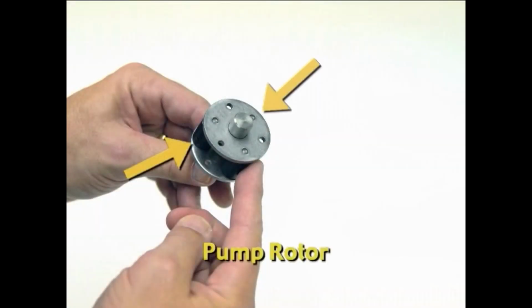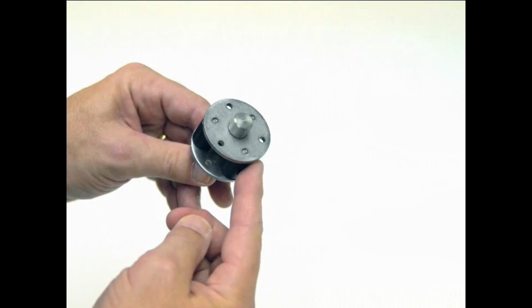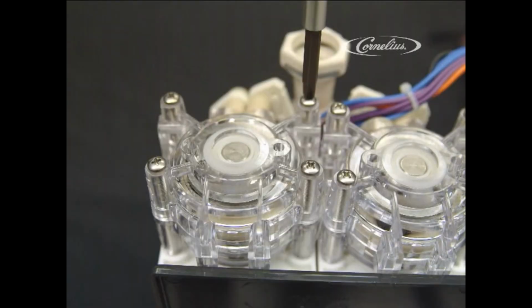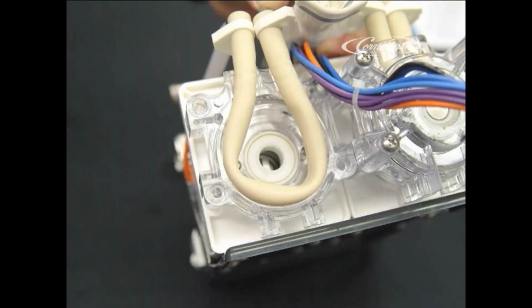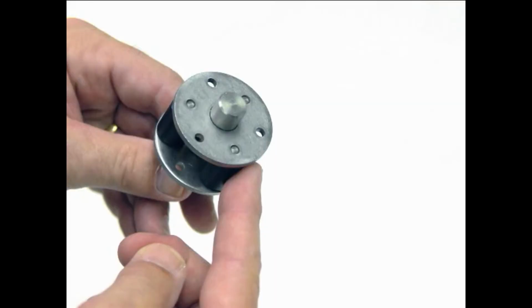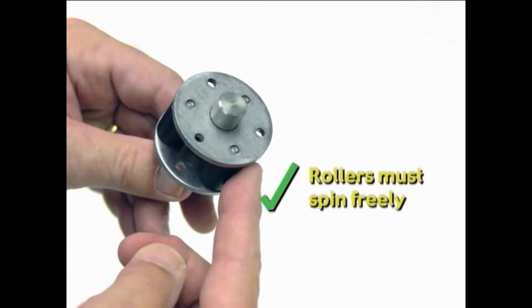The pump rotor has 3 rollers. These rollers must spin freely in order to accurately dose the concentrate into the mixing chamber. The best and easiest check is to pull the rotor out of the pump itself. This is done by removing the 4 screws and separating pump halves. Keep the tubing pushed up and out of the way. Pull the rotor assembly straight off. Spin each roller to check for binding. If found, replace the rotor.